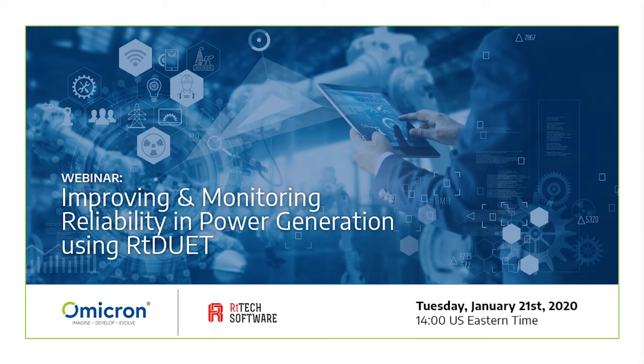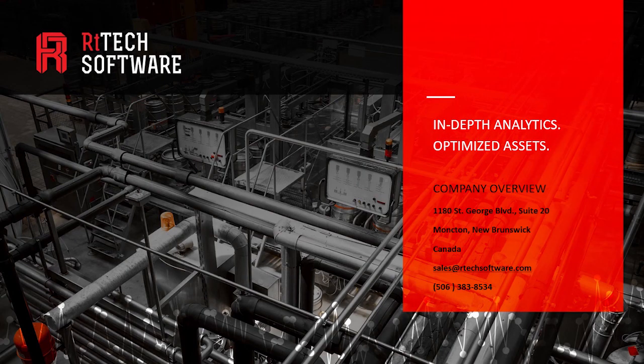However, prior to the rollout, there is the need to do a bit of a workshop to identify the reason tree, because that's one thing that varies from site to site. We need to work with the client to identify the reason tree. If you simply want to implement as per NERC GADS, then that's fairly straightforward. If you have something that needs to be modified a bit, there's a bit of back and forth to identify those. But once that's done, the rollout is pretty straightforward, and usually it requires about 5 days on site to do the installation and commissioning, and another 5 days of training for your users. So it's usually about 2 weeks on site per site.